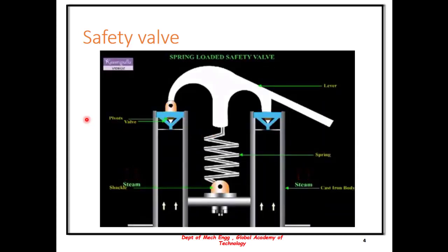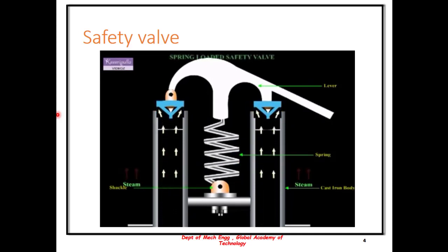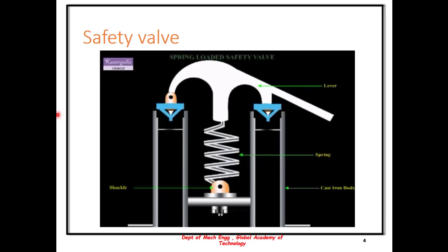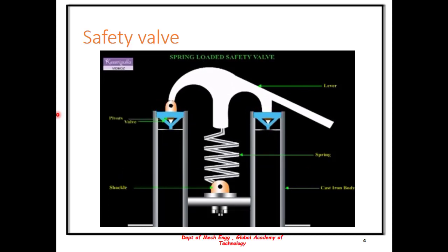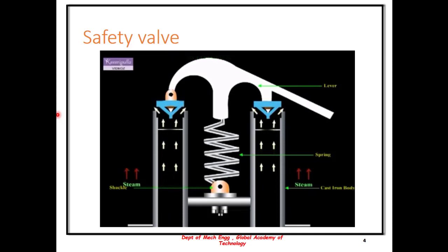The working of the spring loaded safety valve is quite simple. The spring loaded safety valve is loaded by means of a spring instead of weights. It consists of a Y-shaped cast iron body having two limbs called the branch pipes which have valve seats at their top. The two separate valves are placed over the valve seats.